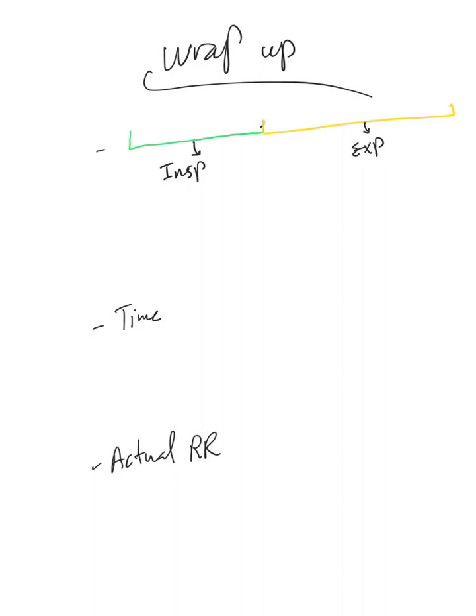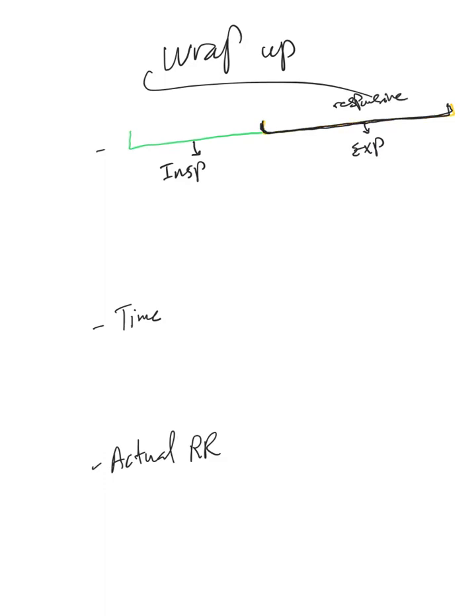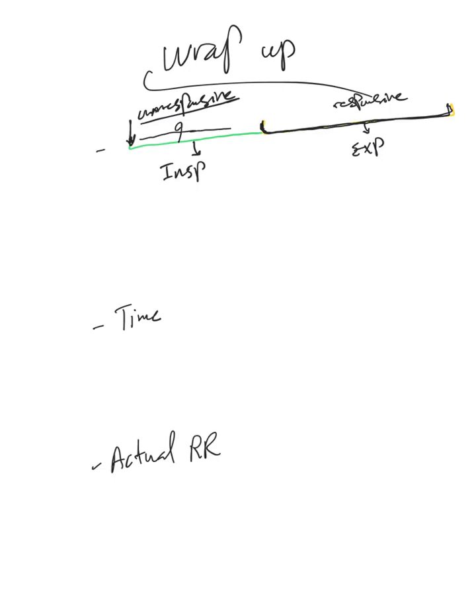One thing I want you to pay attention to is that the ventilator will listen to the triggers from the patient only during expiration. The ventilator is only responsive to trigger during expiration.